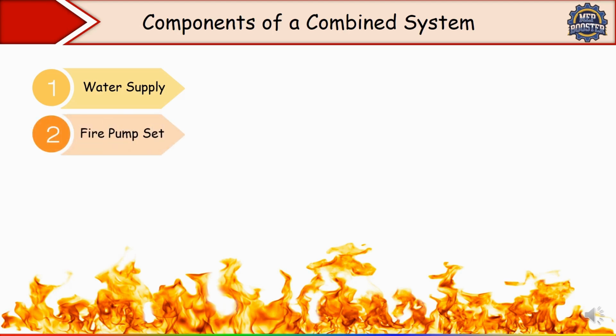Second is the fire pump set. So here we have a main pump, okay, which supplies water to both systems. Main pump means electric pump. Then we have a jockey pump which maintains pressure and prevents false alarm. Then we are using the diesel pump also, backup power for fire emergencies. So these all I have discussed in detail. Okay. Then we have a piping network, common riser for both sprinkler and standpipe. Normally the material which we are using for piping is steel, black or galvanized, or CPVC for small building.